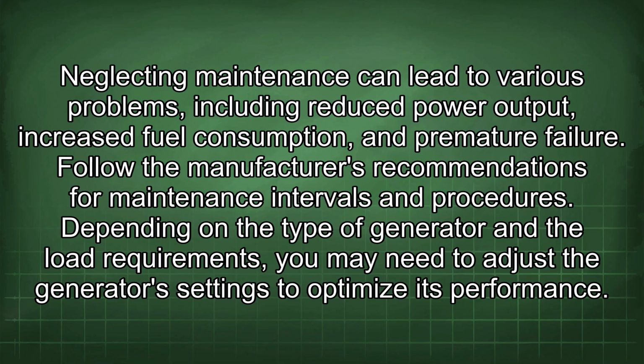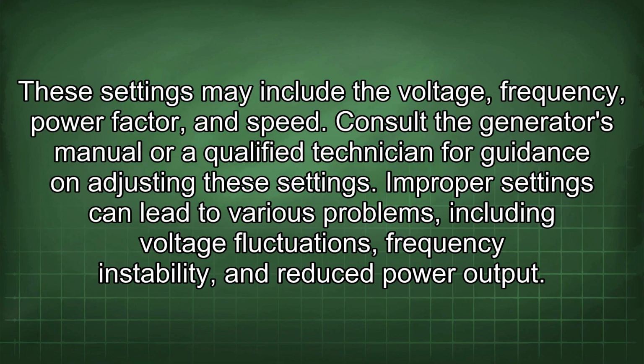Depending on the type of generator and the load requirements, you may need to adjust the generator's settings to optimize its performance. These settings may include the voltage, frequency, power factor, and speed. Consult the generator's manual or a qualified technician for guidance on adjusting these settings. Improper settings can lead to various problems, including voltage fluctuations, frequency instability, and reduced power output.